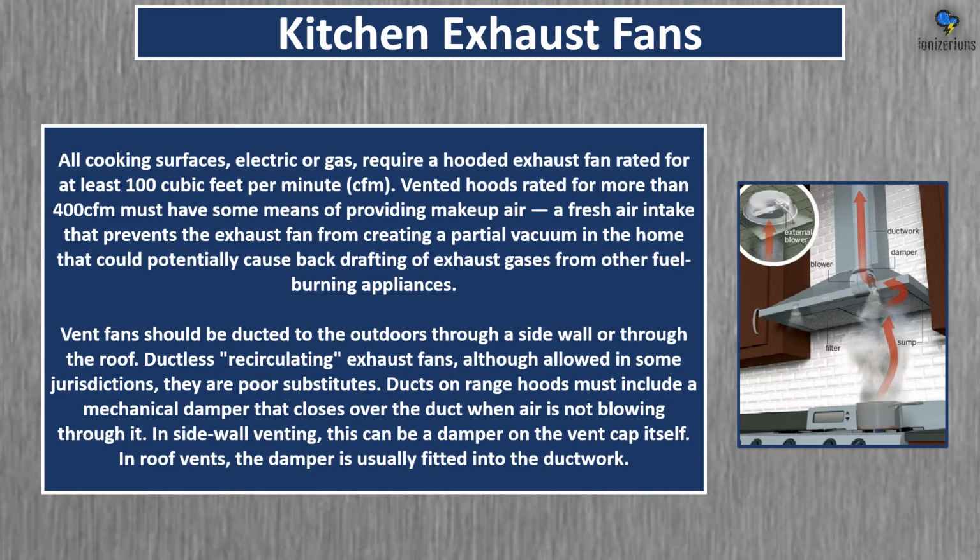Kitchen exhaust fans. All cooking surfaces, electric or gas, require a hooded exhaust fan rated for at least 100 cubic feet per minute. Vented hoods rated for more than 400 CFM must have some means of providing makeup air. A fresh air intake that prevents the exhaust fan from creating a partial vacuum in the home that could potentially cause backdrafting of exhaust gases from other fuel burning appliances.